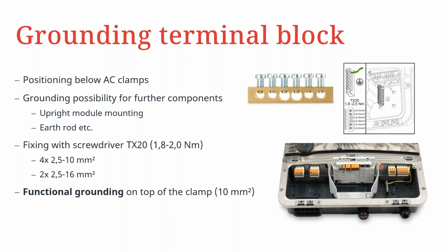And when you connect the PV point, you also need to connect the neutral part of the PV point connection area to this terminal block for earthing. So that we have some bonding there between the PV point and the earthing connection.